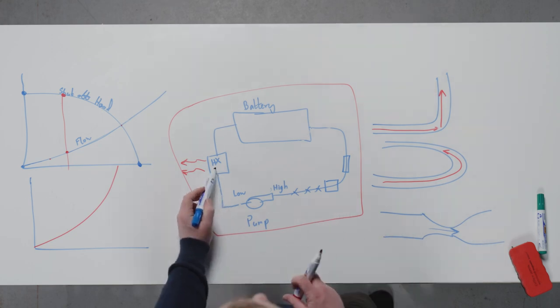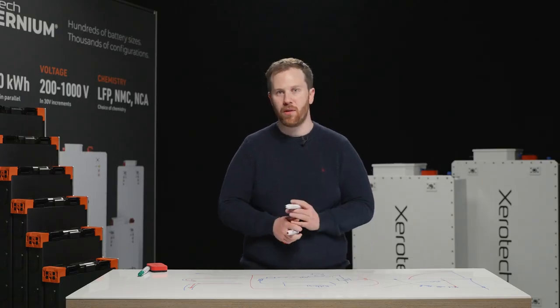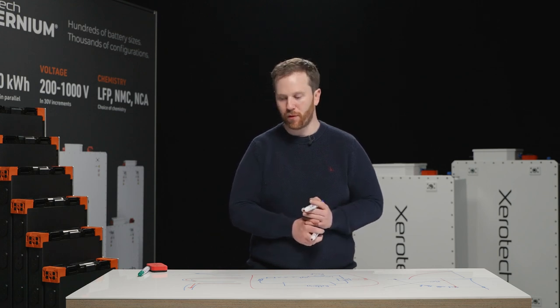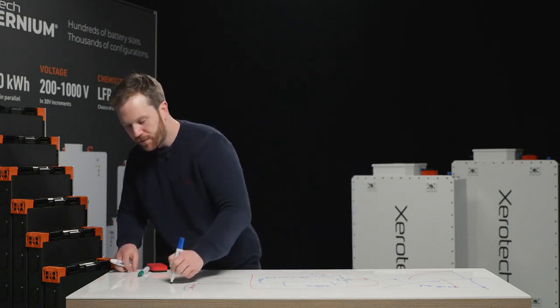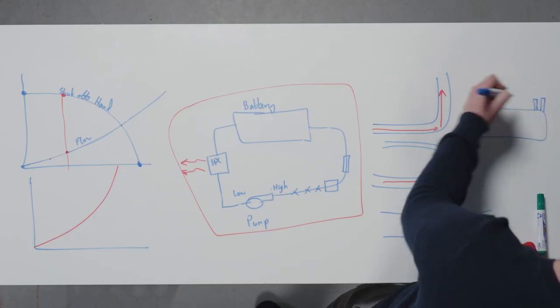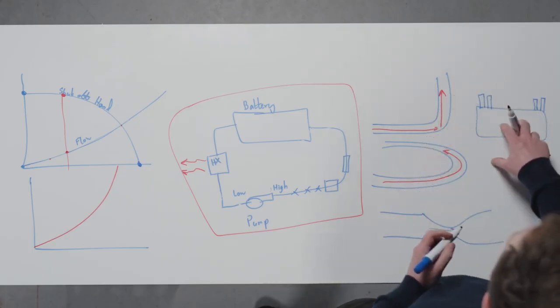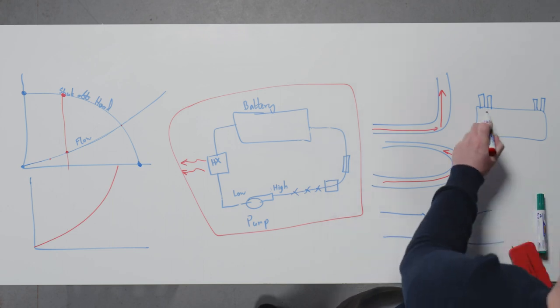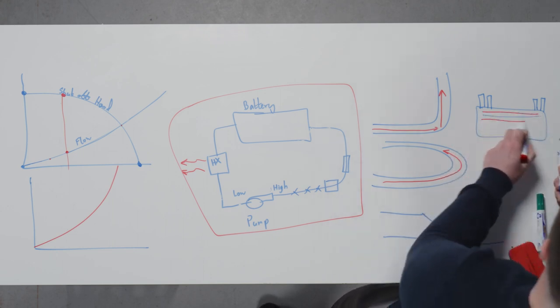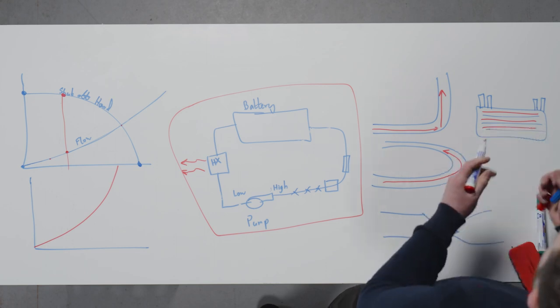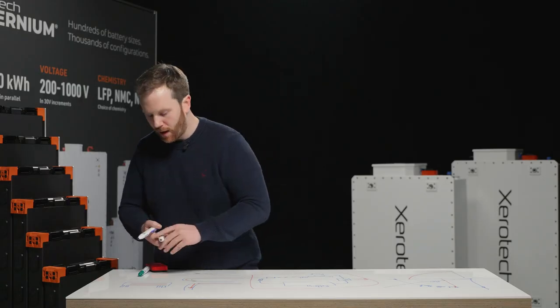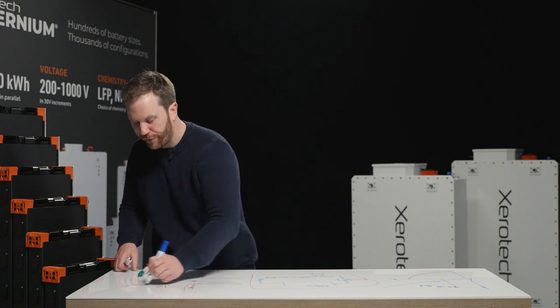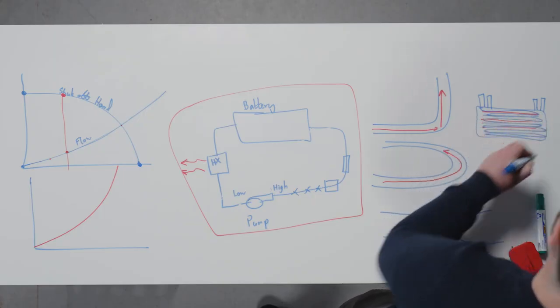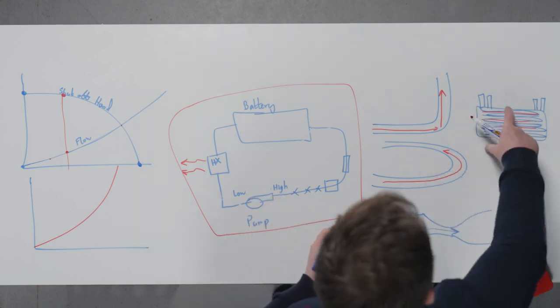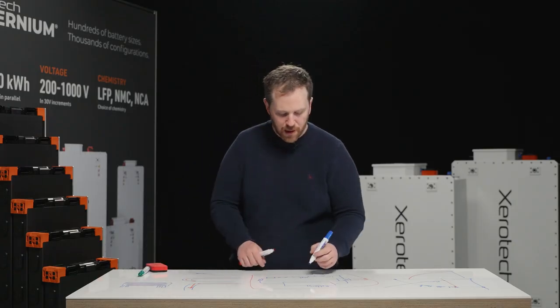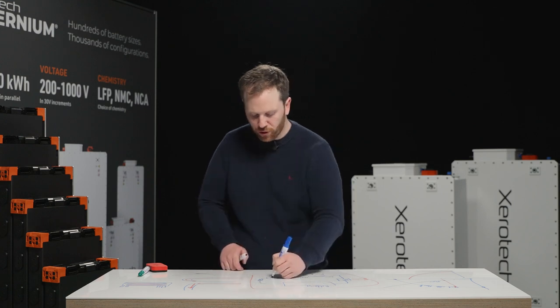So for example, a plate heat exchanger, which is the most common component in a heat pump thermal management system used for battery packs, often looks like a small block with coolant inlet and coolant outlet. These plate heat exchangers have very high pressure drop because it's basically an assembly of lots of alternate plates inside of a brazed plate block. And what the water is having to do is go through a very convoluted path, constantly changing directions, very narrow openings. These components have very high pressure drop.